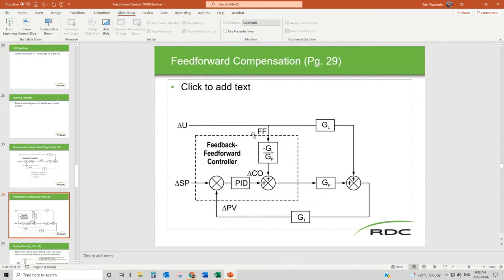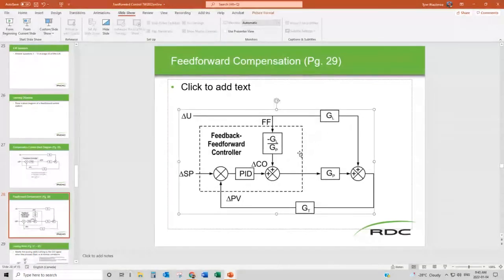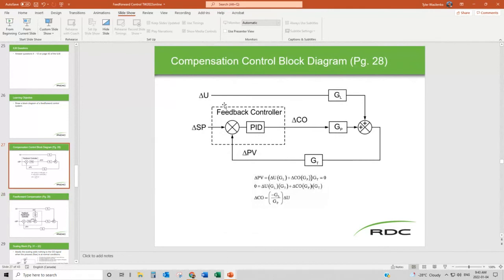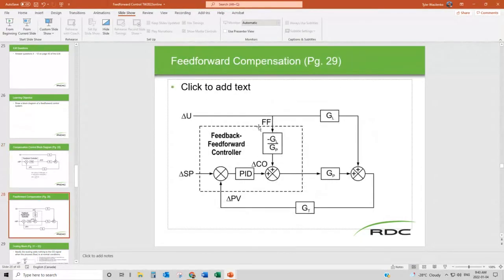Okay, adding feed forward compensation to this is done by using this feed forward controller and the new parameter that we figured out through our math there, the difference in the gain of the load disturbance and the gain of the process. So ultimately what we're doing when we're implementing a feed forward process is we're addressing the effect of the load disturbance on the process. And in order to do that, we do a test of each process to see how it reacts, and then we make a ratio, basically taking a dividing line here, and we're providing a ratio that gets applied to our controller output. So this is the key block in a feed-forward compensation block. So feedback controller, you see we're missing that block. Feed forward, we have this block.